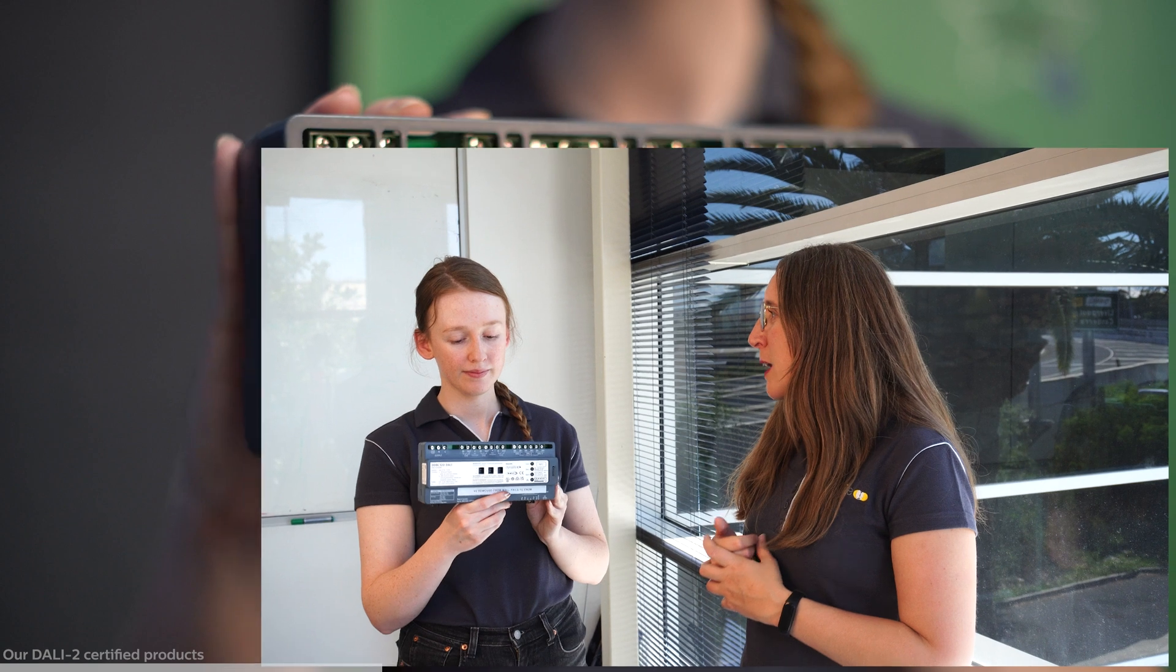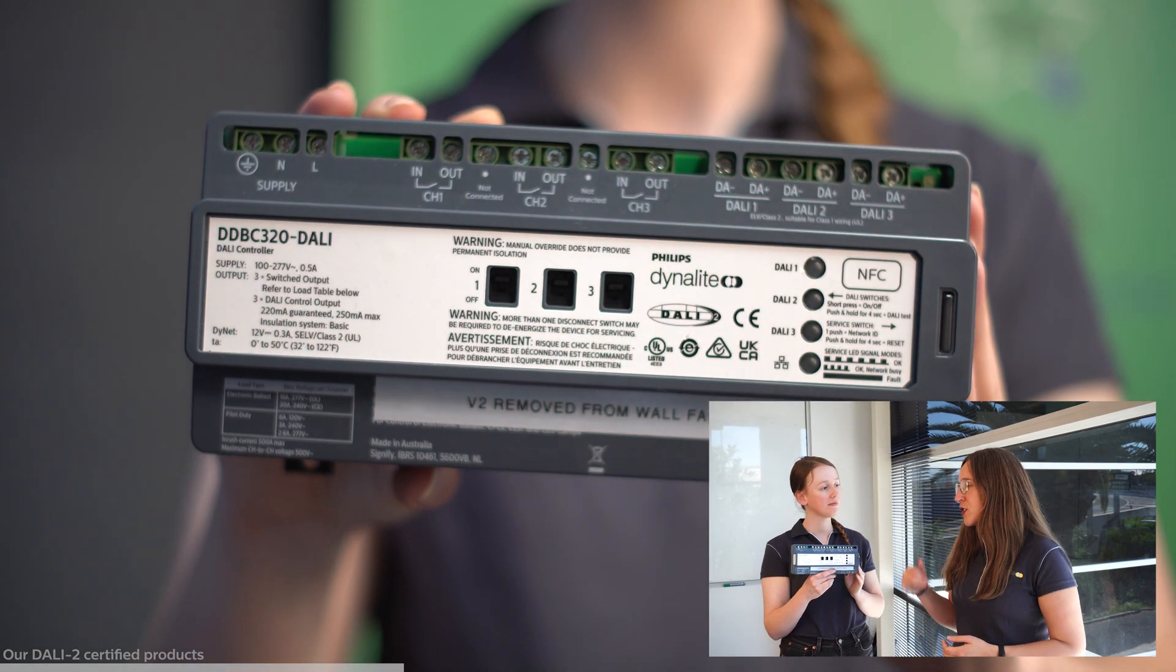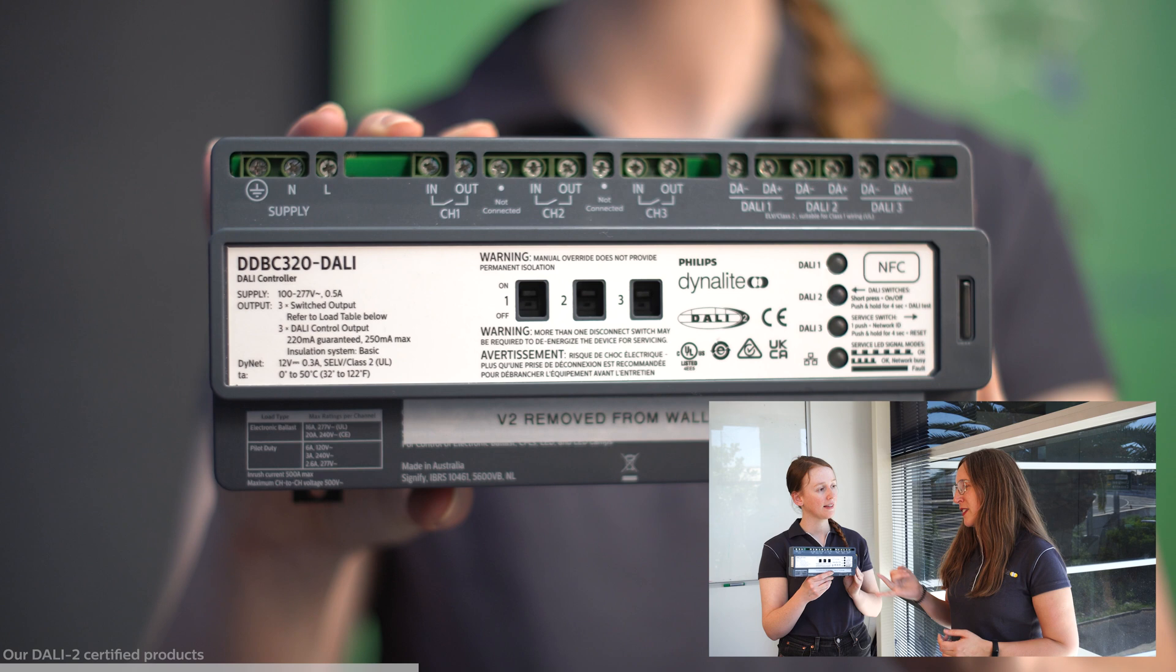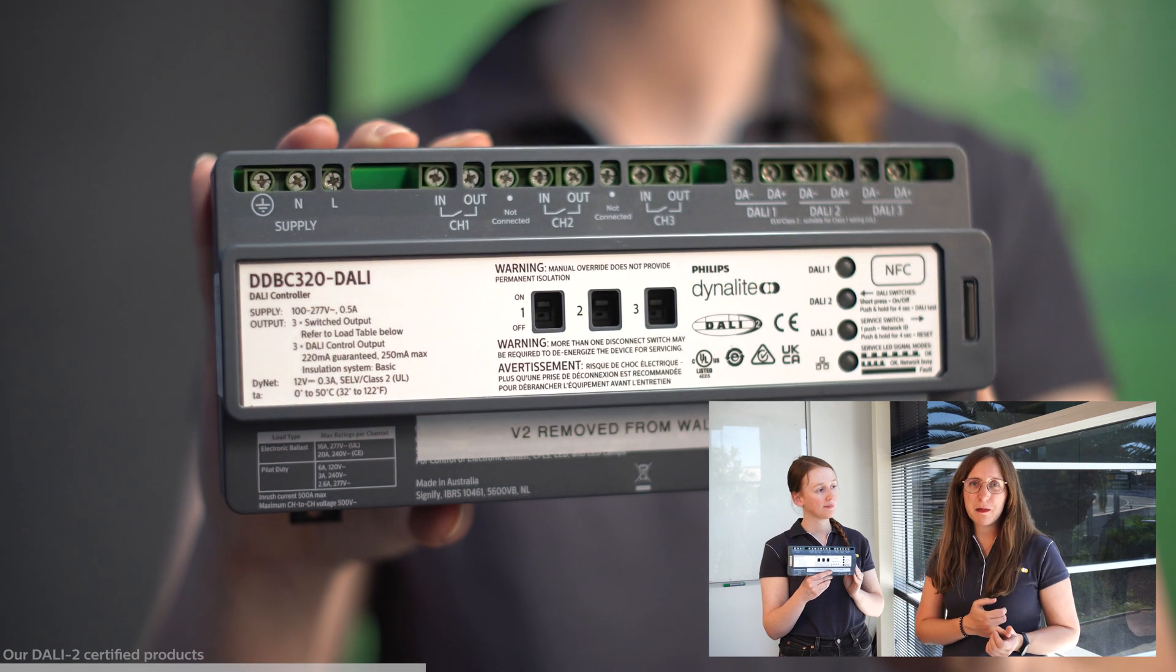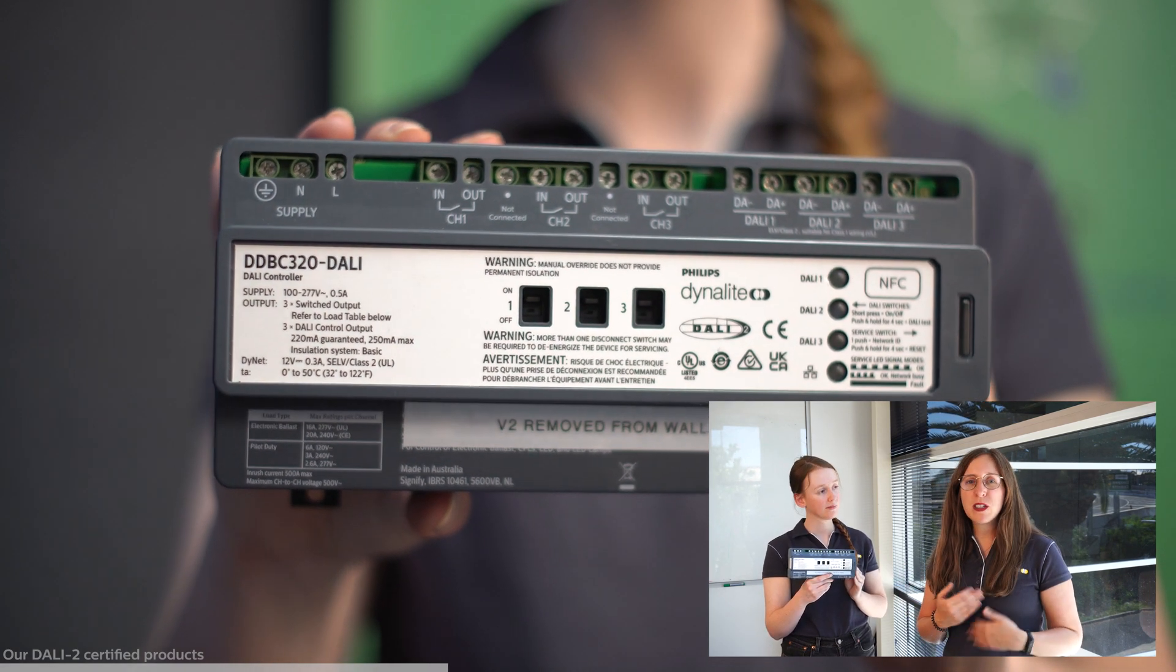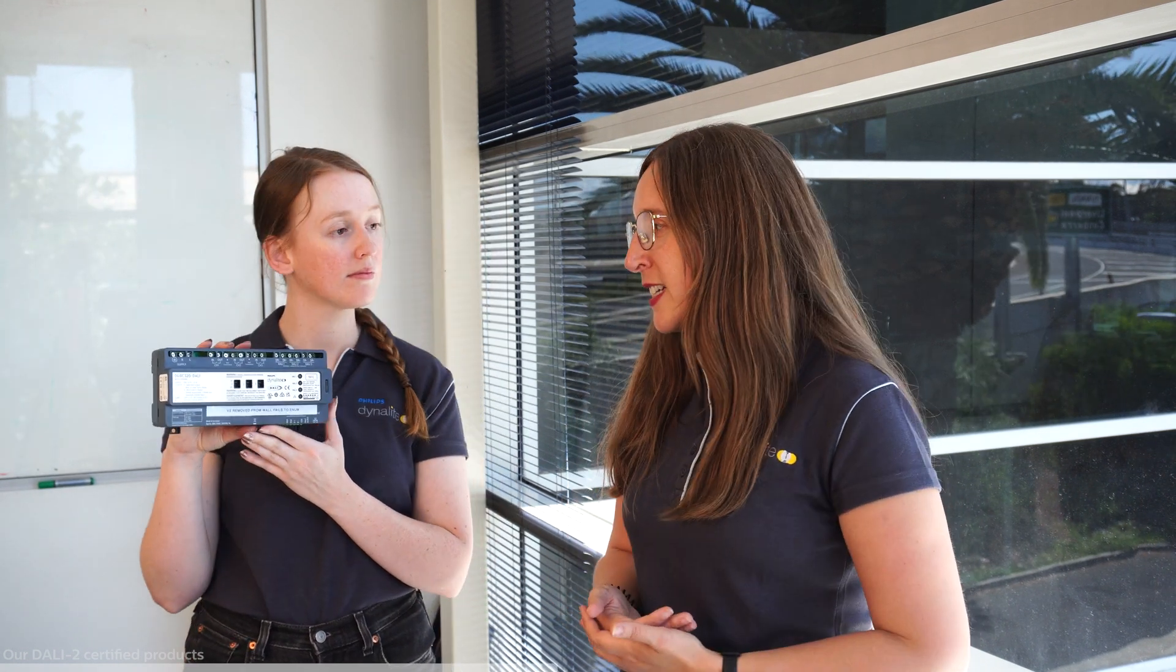We have a power supply included in the controller and also this small relay enables us to enhance energy savings by cutting off the 0.5 Watt energy consumption from each driver when all the luminaires inside the controller are off. Now let's go for the DDBC320-DALI. Okay so here we have a more cost-effective solution because we have for bigger projects a three universe controller. Now we can go up to 192 drivers. We have the same features of power supplies included. We have the DALY direct mapping with Dynet. We have the relays but what's more? So we have an inbuilt ethernet port to securely communicate for example with our PDEC-S which is our ethernet secure gateway. We also have a relay suitable for North America so the UL924 which enables emergency lighting.